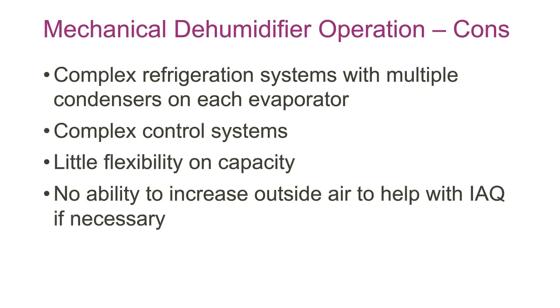On the downside, they are relatively complex and are prone to failures. They have multiple condensers on each evaporator, so you have a refrigeration system that typically has 3 condensers operating on one evaporator, and that is a challenge on refrigeration. The control systems for them are also quite complex to control whether to heat water, to heat air, where to send the refrigeration. They don't have a lot of flexibility.